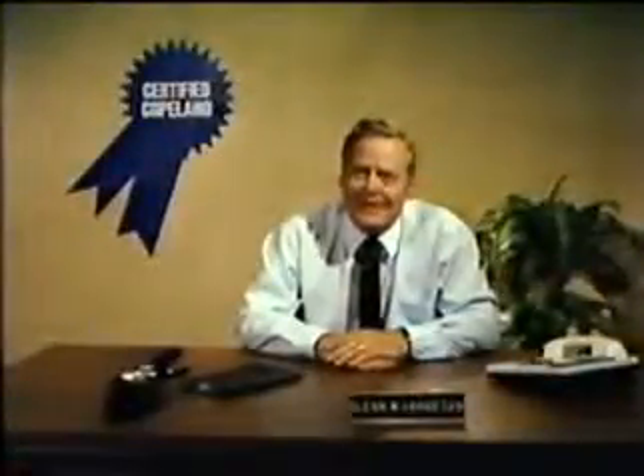Hi, my name is Glenn Hannigan. I'd like to help you understand some of the common causes of compressor failures. When looking into this subject, you have to start with one very interesting fact. Industry records clearly show that replacement compressors, whether they are new or remanufactured, fail at a rate many times greater than compressors going into new systems.